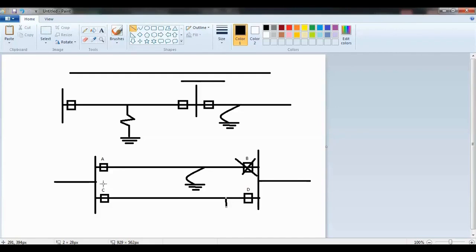Previously, I told you that there is a feature present in the MICOM. As I mentioned, in the MICOM, it was written as Aided/Z1. What was written on the send counter? If a communication failure occurs, it will become a carrier. The second case is if an evolving fault occurs. The term Aided/Z1 indicates that if the device trips in zone 1, it will become a carrier sender to the other side. So it understands what an evolving fault is. We will see how this is done now, okay? Now to simulate this, here we go.